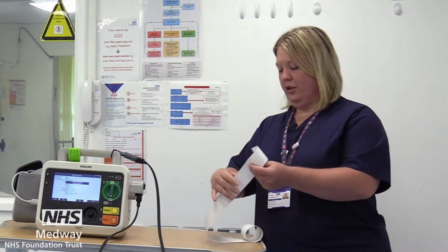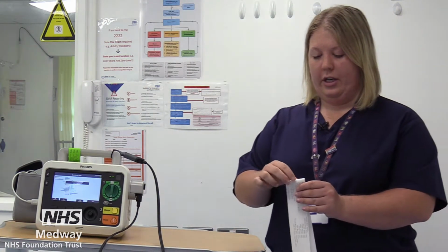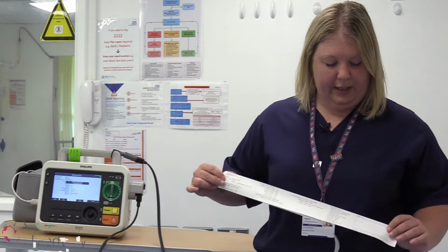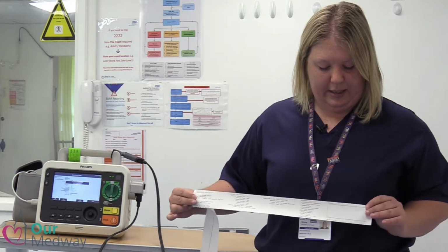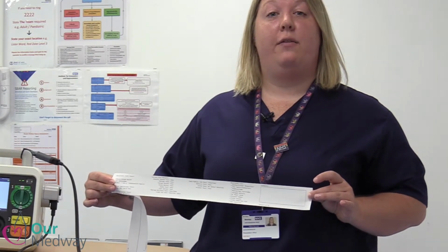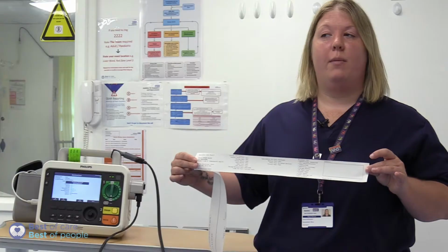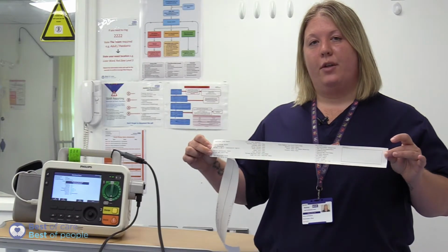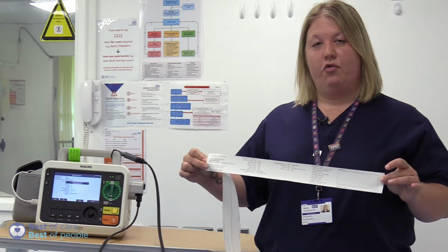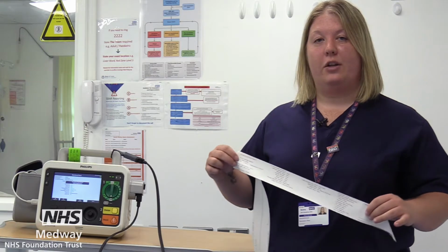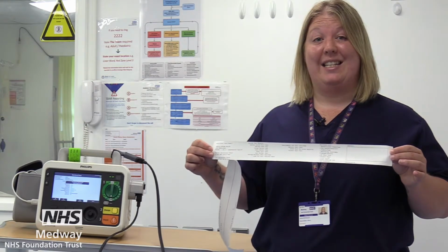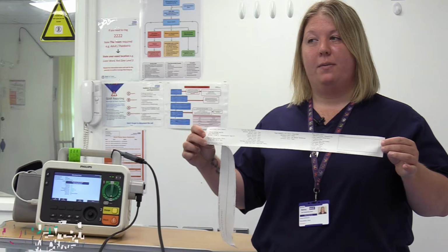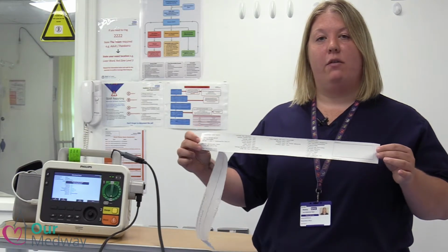One thing I'd like to show you just on this operational check part here is that there is a box at the end for you to sign. So the operator who did the check, if you sign, and then there's a box there for any comments that you need to make. I would keep this monthly operational strip that's been signed, and I would keep it within the month that's appropriate as per your emergency trolley checklist, as proof that you've done it and as proof that there's been no incidences or errors with your defibrillator as well.